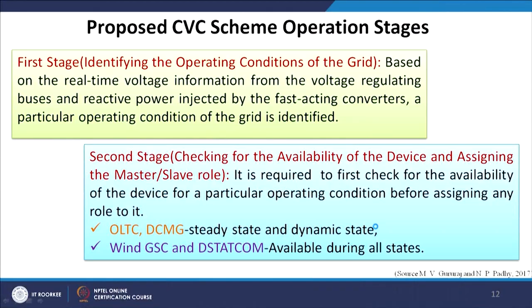It is required to first check the availability of the device for a particular operating condition before assigning any role. For example, OLTC and DC microgrid are used during steady state and dynamic state, whereas wind generators and DSTATCOMs are available throughout all three states. The final step involves introducing a time delay in operation — if you want a slow device to act before fast devices, a delay in action on those fast devices can be incorporated so that slow devices inject reactive power first.